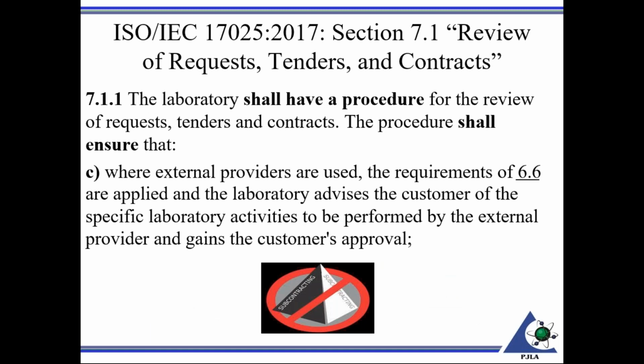The procedure shall ensure where external providers are used, the requirements of 6.6, which is the section on externally provided products and services, i.e. purchasing, are applied, and the laboratory advises the customer of the specific laboratory activities to be performed by the external provider and gains the customer's approval. So if you're not aware, section 6.6 is purchasing, is also subcontracting. So in the realm of 7.1.1(c), we're talking about subcontracting here.